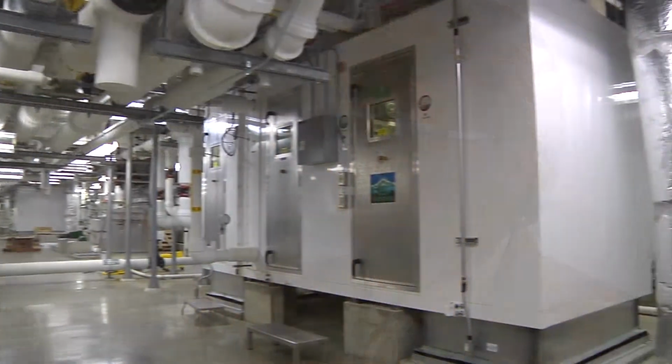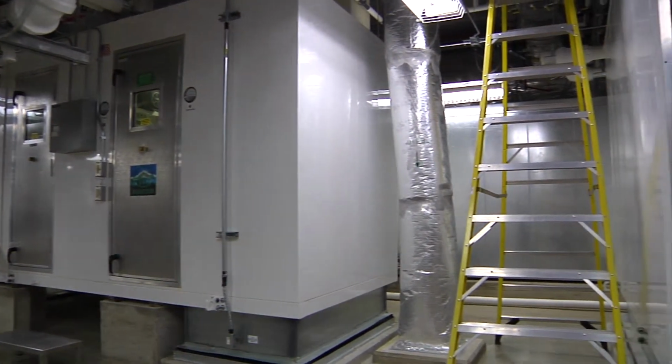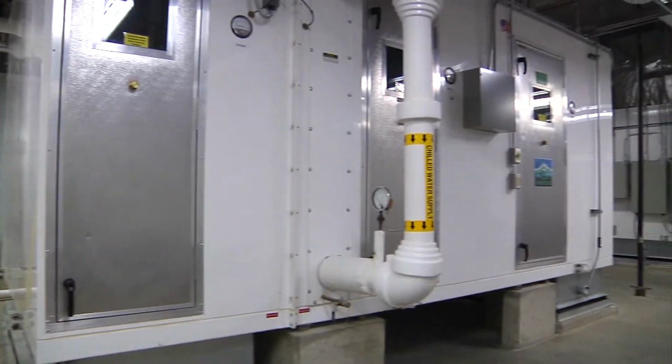The recirculating air handlers have filtration, fans, and sensible cooling. In other words, it senses the temperature inside the clean room and adjusts the cooling according to that. You don't need to add any heat to the air because the friction of moving that air through the ducts adds plenty of heat. So by controlling the cooling rate of the air in there, we can control temperature stability very, very carefully. This air then flows down through the clean room, under the floor, back up through the chase, and back into that recirculating air handler.